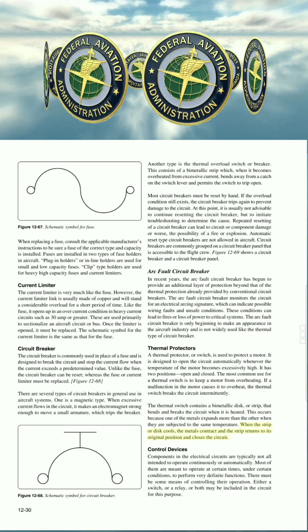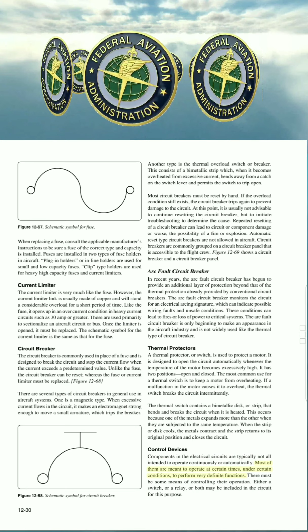Thermal protectors. A thermal protector, or switch, is used to protect a motor. It is designed to open the circuit automatically whenever the temperature of the motor becomes excessively high. It has two positions, opened and closed. The most common use for a thermal switch is to keep a motor from overheating. If a malfunction in the motor causes it to overheat, the thermal switch breaks the circuit intermittently. The thermal switch contains a bimetallic disc, or strip, that bends and breaks the circuit when it is heated. This occurs because one of the metals expands more than the other when they are subjected to the same temperature. When the strip or disc cools, the metals contract and the strip returns to its original position and closes the circuit.